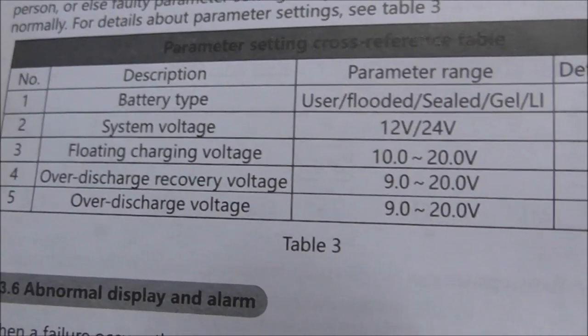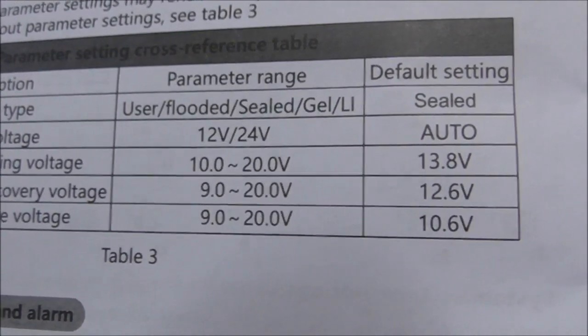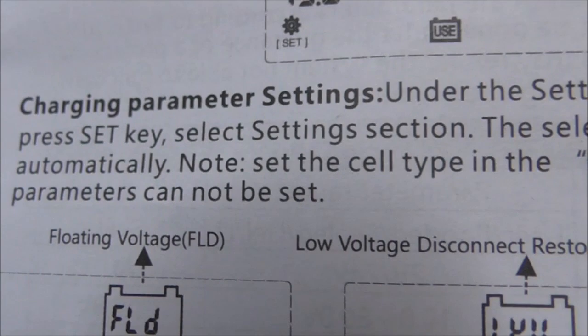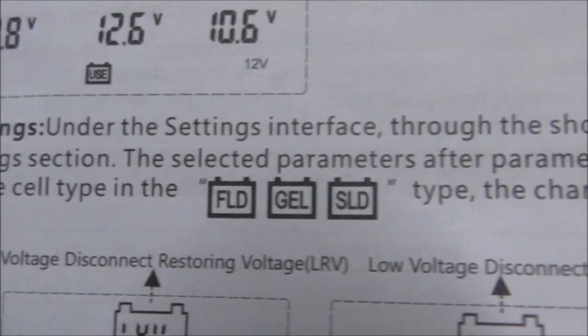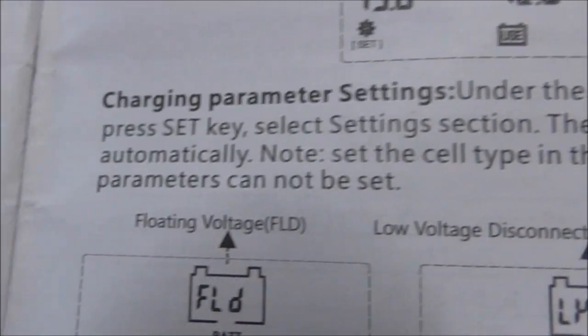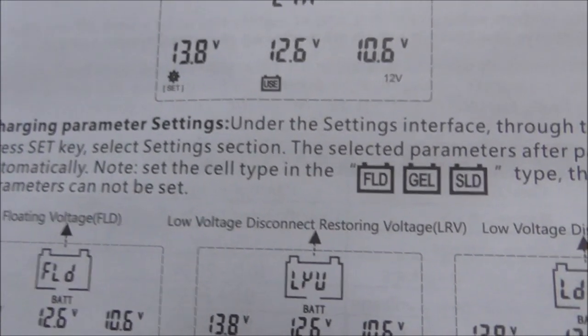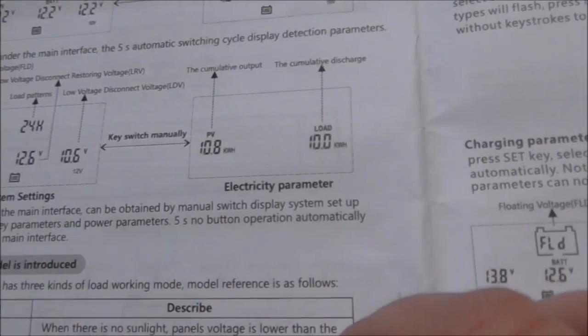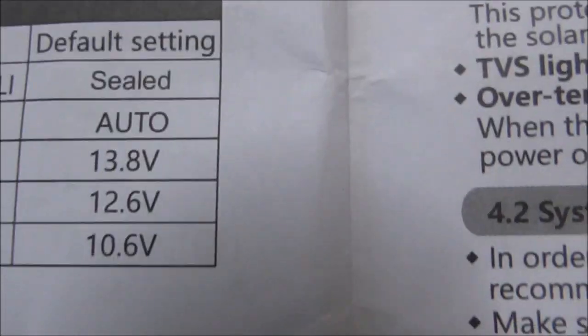You can adjust the float, over-discharge recovery, and over-discharge voltage over a long range, but it's got an auto setting. It says: note, set the cell type to the flooded, gel, or sealed type - the charging parameters cannot be set. So that tells me when you select any of those three, the parameters are fixed and you can't adjust them; you have to go by the default setting.